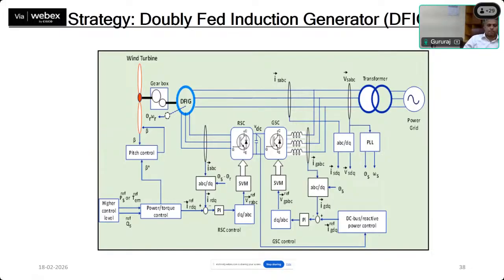So what will happen now is there is an immediate impact as seen on the rotor side. That impact is seen in terms of increased voltage, because the relative speed variation is quite large, a DC flux cut by a high rotating mass, and the EMF gets induced according to Faraday's law of electromagnetic induction. This dynamically induced EMF, by the flux cutting principle, is rated way above the capacity of these converters, and the switches may have to carry a large amount of current which they are not supposed to carry. This extra power pulled by the switches is reflected across the DC link capacitor, which is a vulnerable device that may blow off.